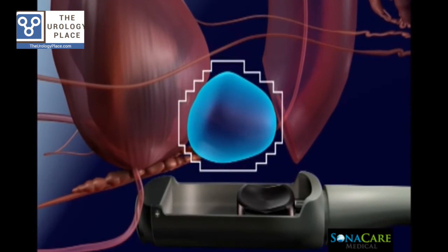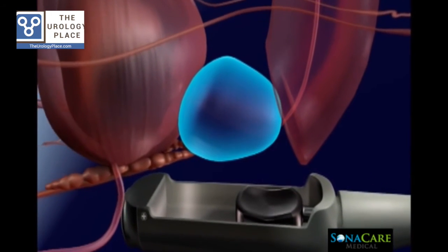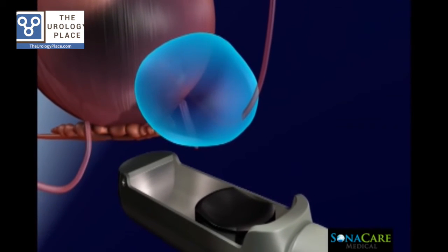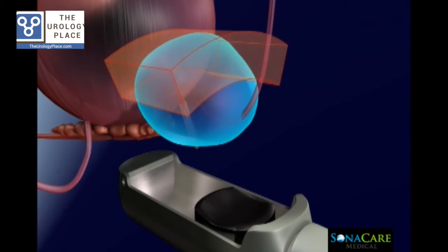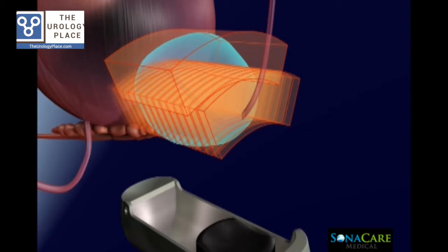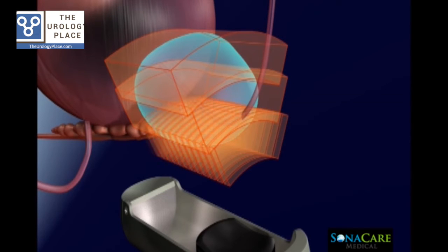In preparation for ablation planning, the Sonablate Imaging Transducer maps the morphology of the prostate gland in real-time. This allows the physician to create a customized plan for the procedure in multiple ablation zones. The device makes use of integrated bi-planar ultrasound imaging for real-time ablation planning, monitoring, and post-ablation imaging.